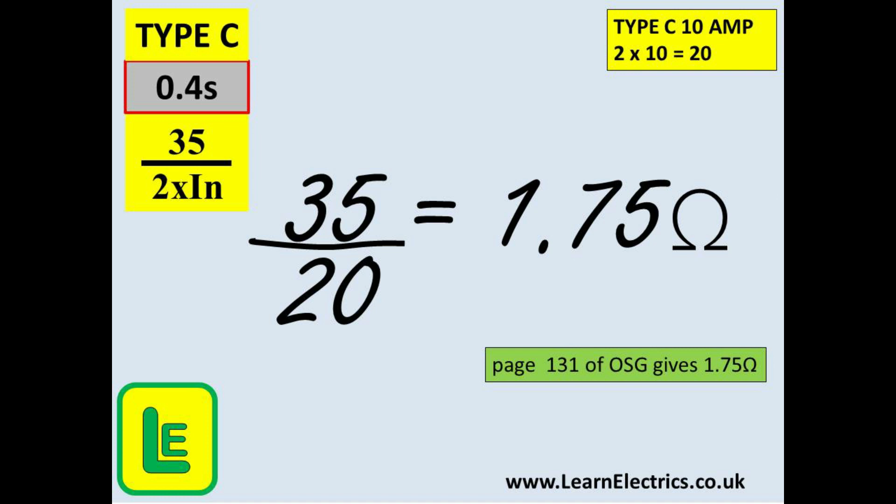We will stay with the 10 amp breaker which is now a type C. For the formula we will double the 10 amp rating and this will give us 20. Our formula then is 35 divided by 20. Pop this into a calculator and we have 1.75 ohms. Table B6 on page 131 of the on-site guide tells us the maximum ZS should not exceed 1.75 ohms. Again it is spot on and as your confidence grows you will trust your calculations when you are on-site without a book.